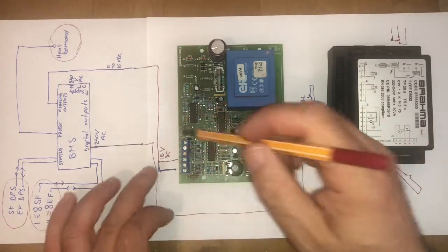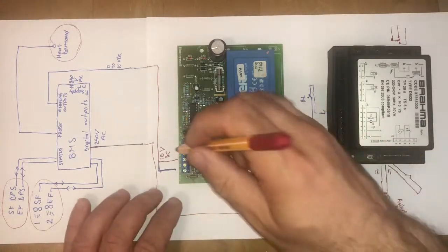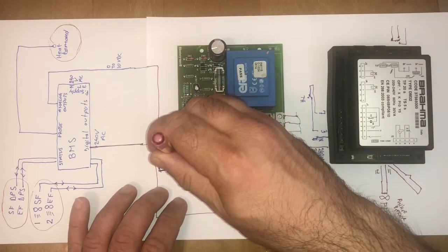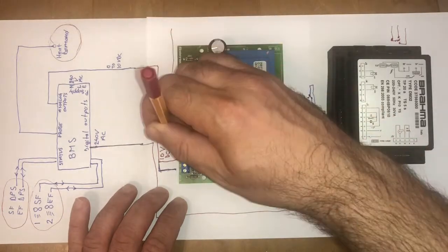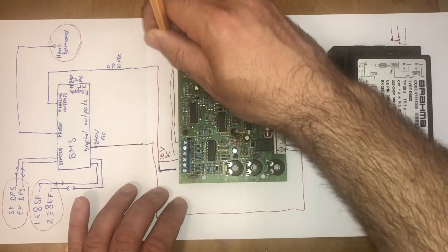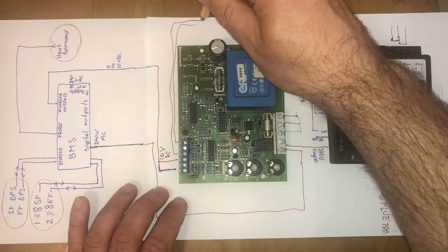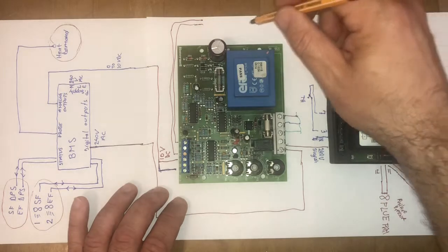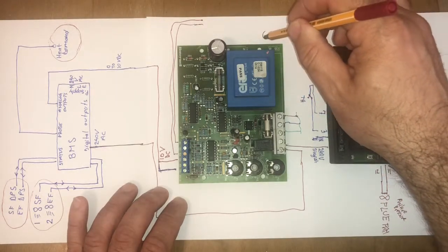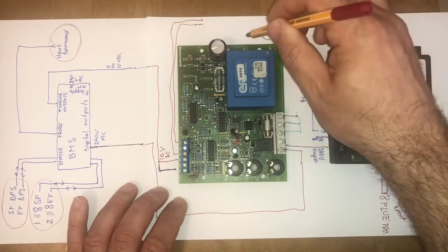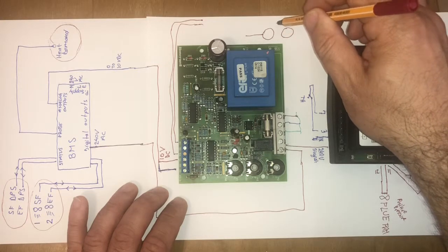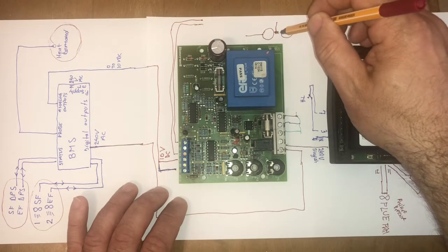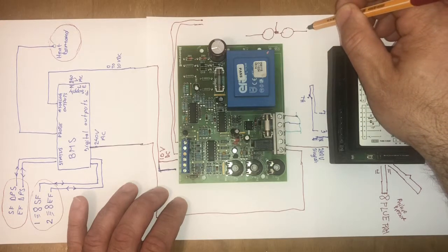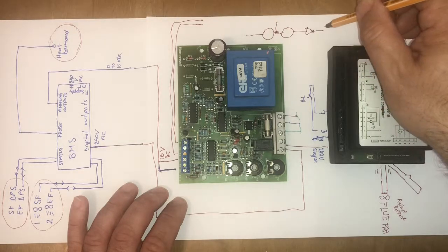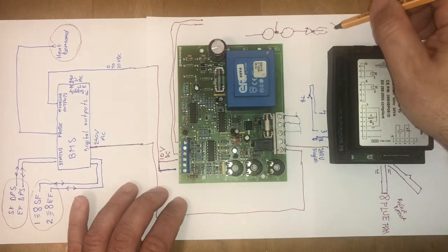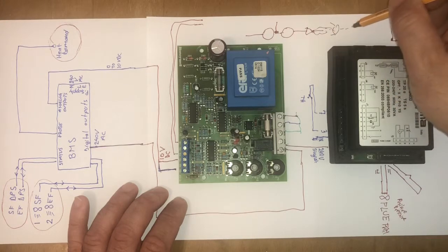One of the bad things, if you do this little override, is that it will affect this, and I'll explain to you what this is. The gas valve. You have two gas valves with two solenoids. I'll try to make you understand. You have the first gas valve, you have the second gas valve, so the gas passes through one, and here I have an actuator, and then the second gas valve, and then you have the burner, and then you have the flame here, and then obviously you have the tubes where the flame goes inside and is sucked by the flue fan.